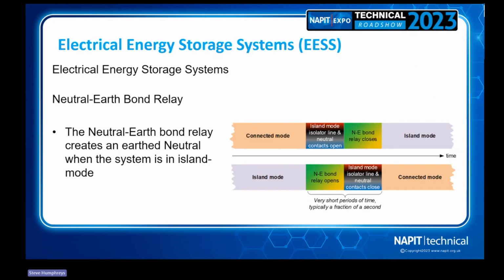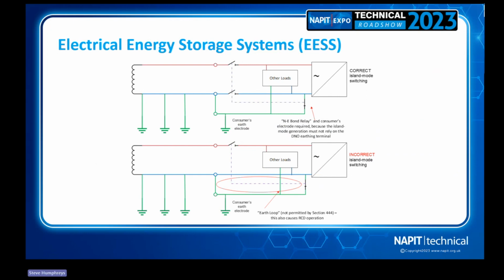And again, that relates to this thing called the neutral earth bond relay. So this is where in connected mode, what would happen as soon as it goes into island mode, the island mode isolator line and neutral open, and then the neutral bond relay closes. And that's done in a fraction of a second when it goes into island mode. Now, like you saw in that picture of the Tesla Powerwall, that could all be done internally, or it could be external components that sit outside. And this is the reason why.